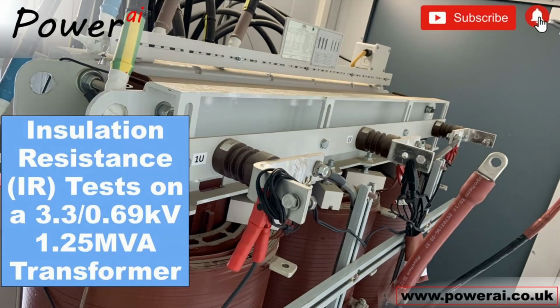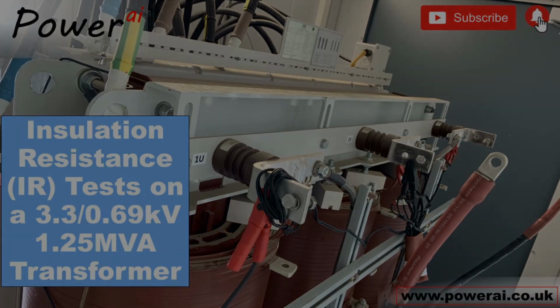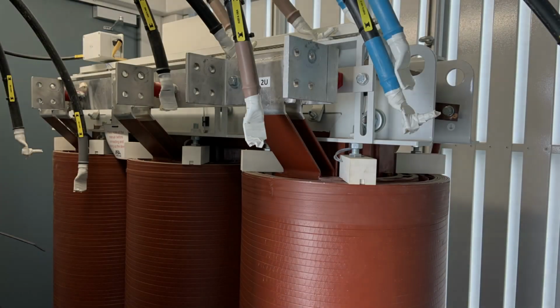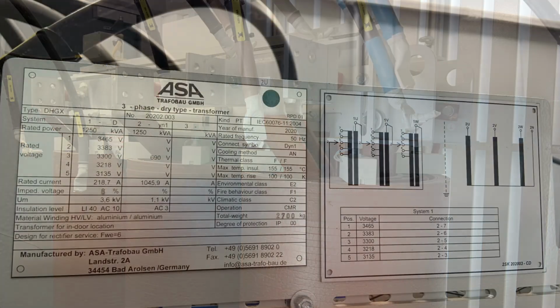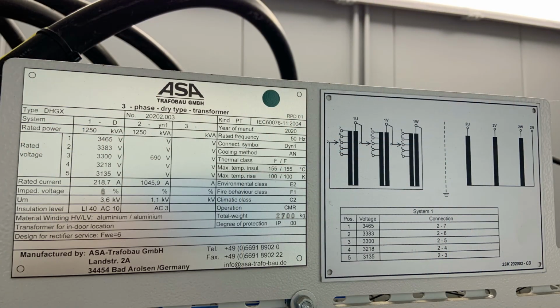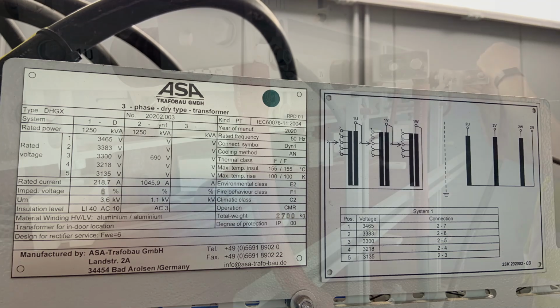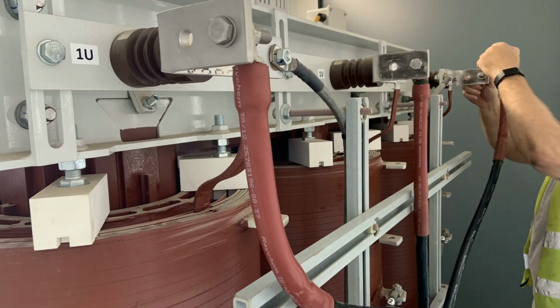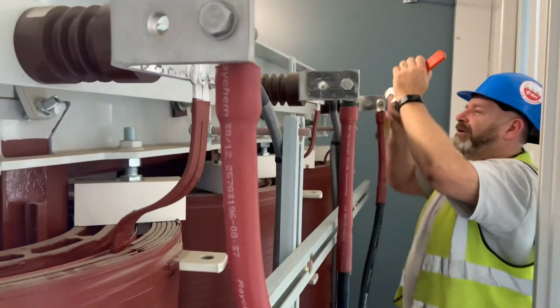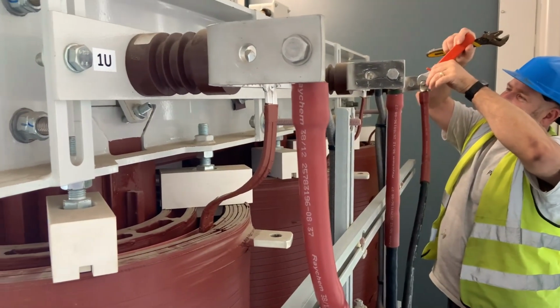In this video we demonstrate 3 basic insulation resistance tests to the windings of this cast resin transformer. This particular one is a 1.25 MVA, 3.3 kV down to 690 volts, cast resin dry transformer. First we want to disconnect all the cabling on the HV and the LV sides.